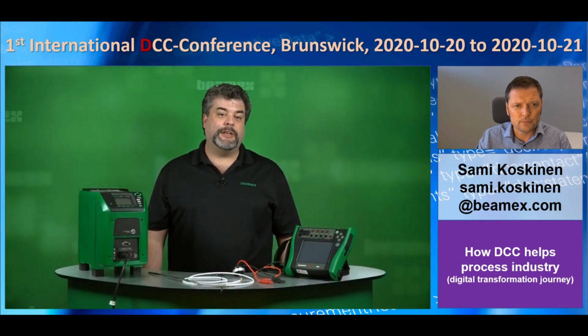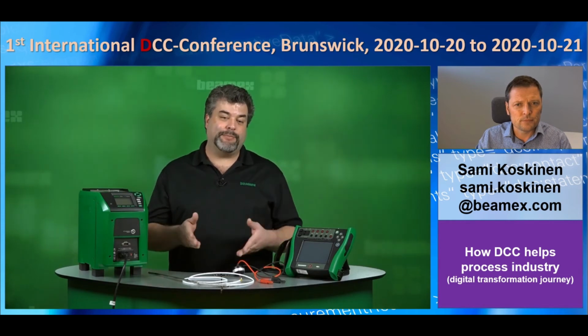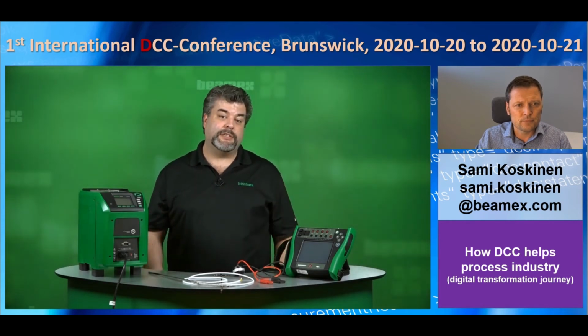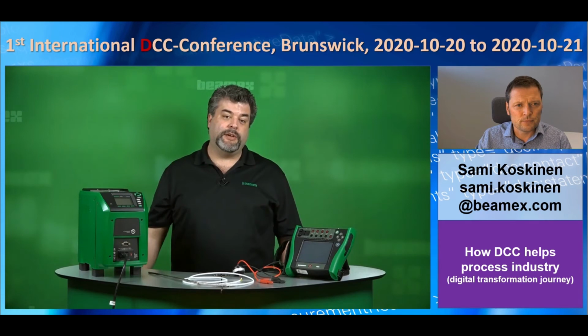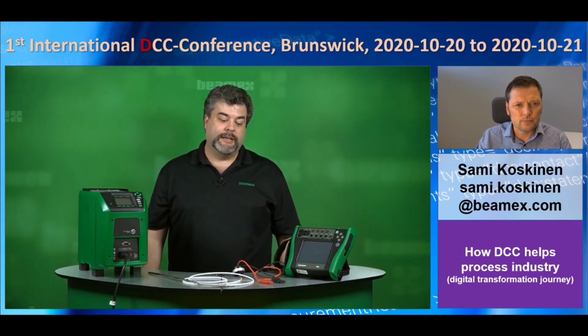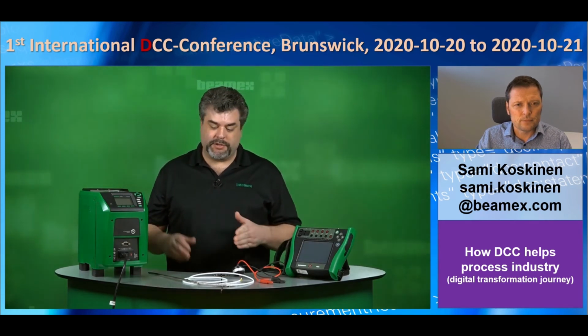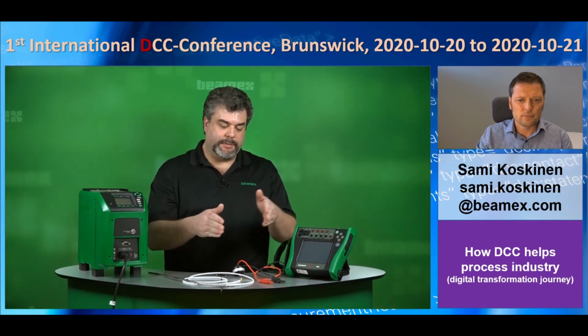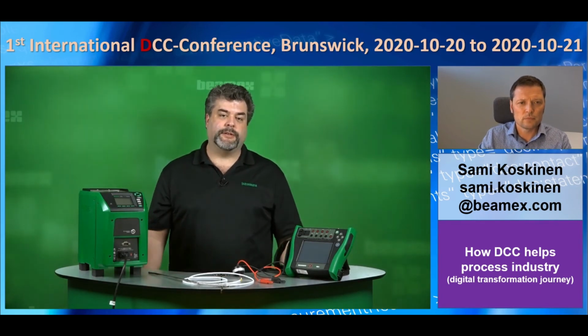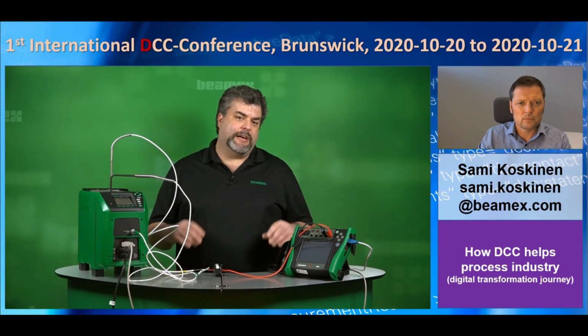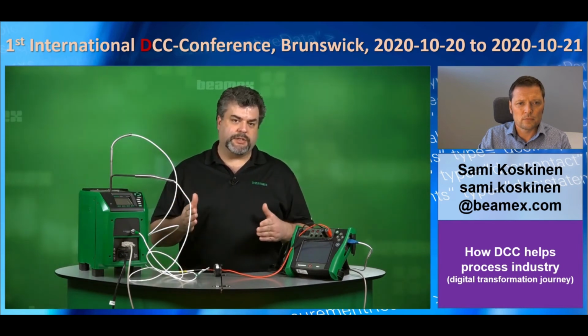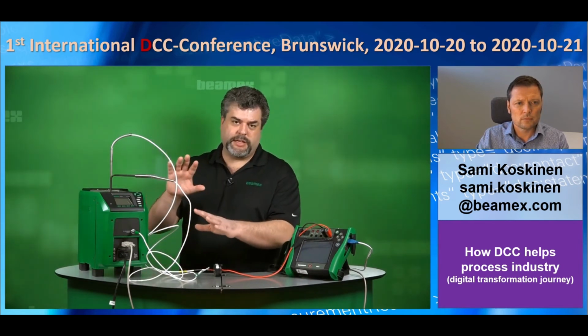And during this short video, I'll show you how to calibrate a temperature loop using a Beamex MC6 and a Beamex FB150 dry block. We'll be doing this as an automatic calibration, calibrating this temperature element and this temperature transmitter. Continuing doing an automatic calibration, we need to make the connections. So let's break this down.